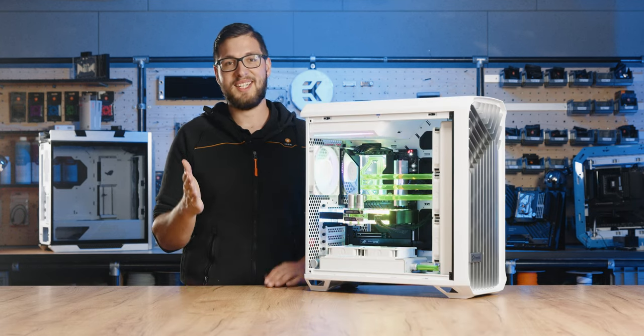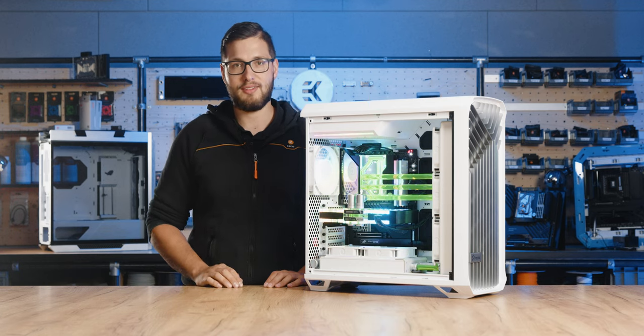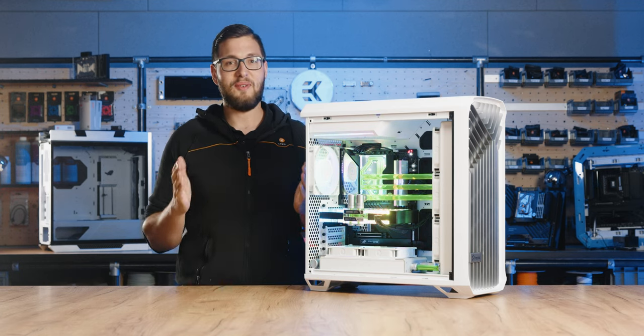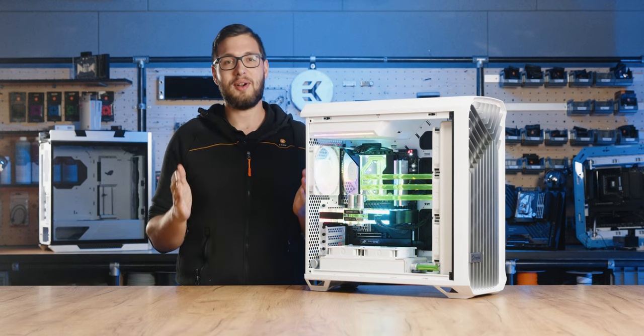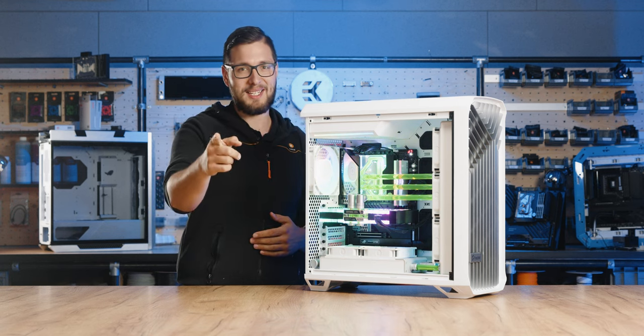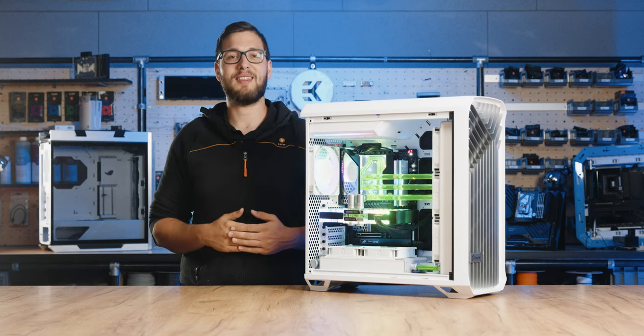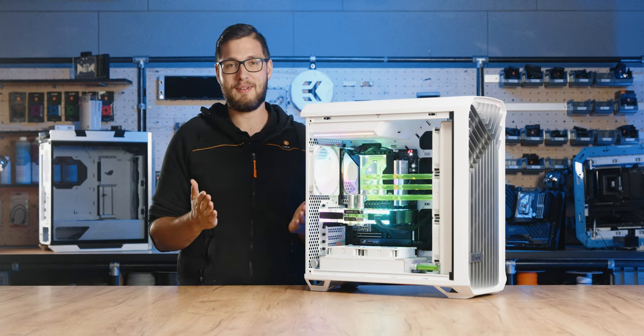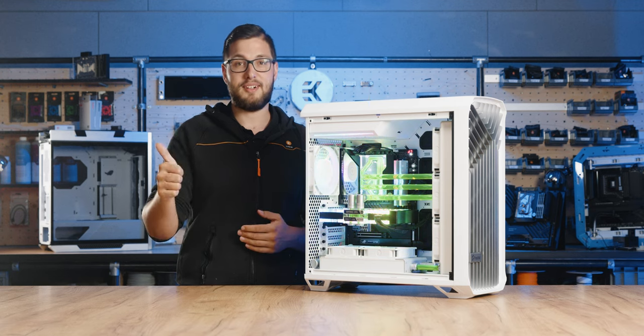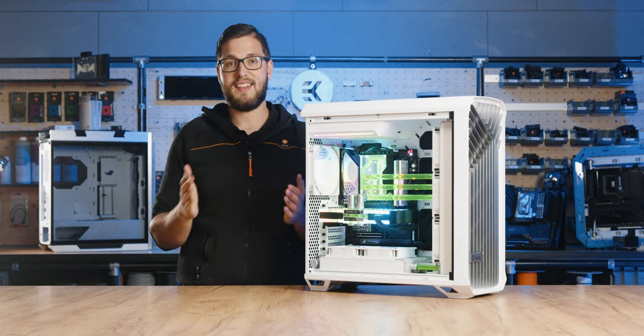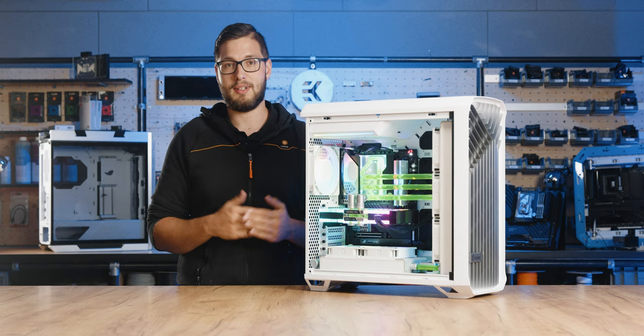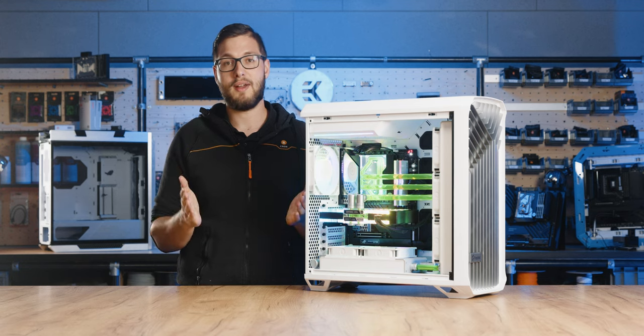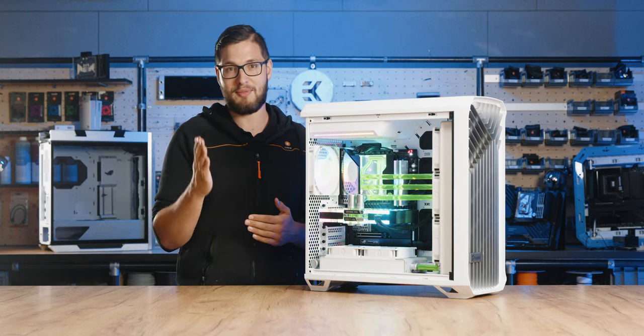You know that saying, failing to plan is planning to fail. If you watched the video so far, you probably know where I'm going with this. It's loop planning time. So your future self can thank you for simplifying the maintenance process. First, you install the drain valve. Then ensure it's at the lowest possible position in the loop, so you can count on gravity to help with drainage.